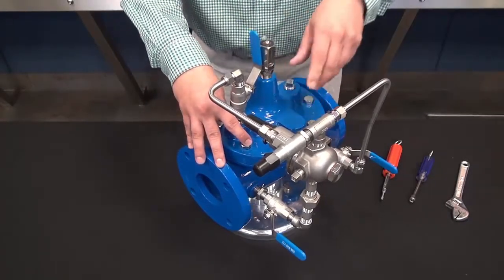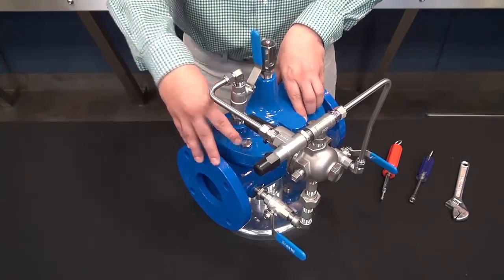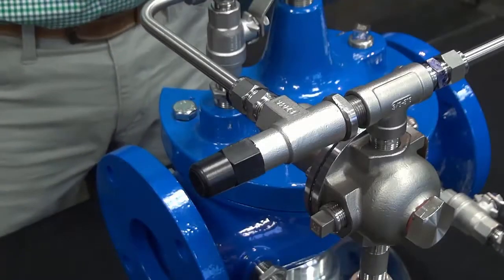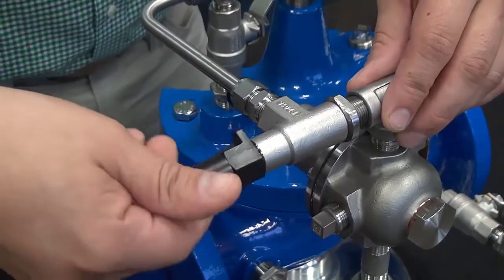On valves four inch and larger, opening and closing speed controls are both optional features. We want to make sure that the speed control is backed out and out of the way when we are setting this valve.